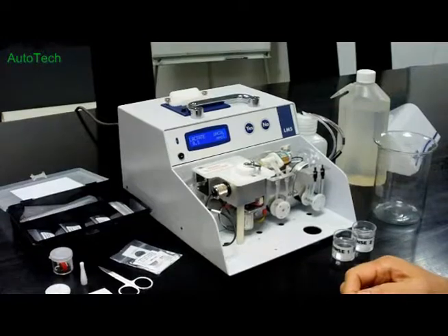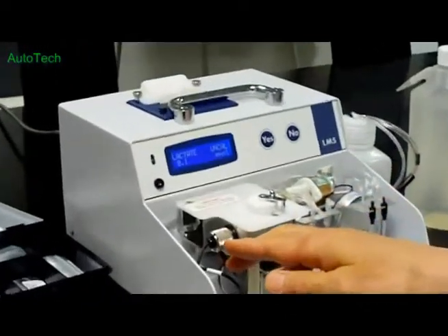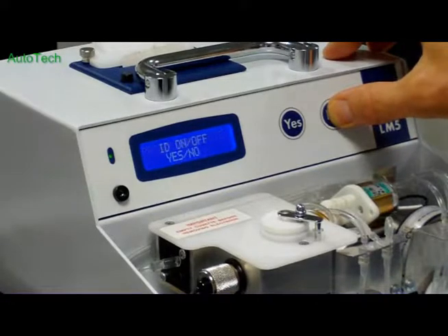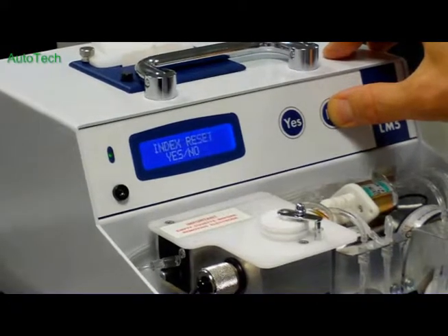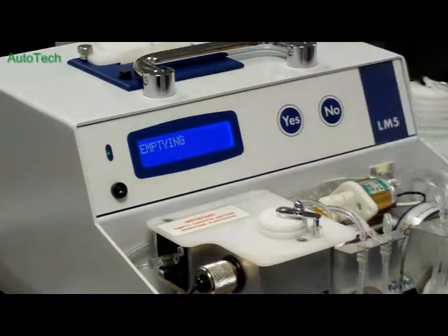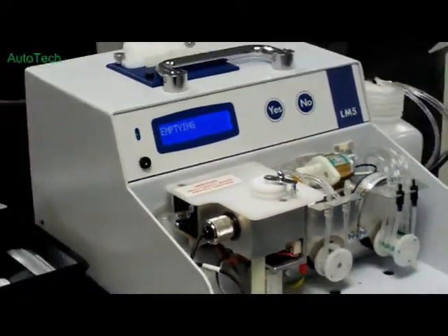And then it's most important that you empty the reaction chamber before removing the electrode. So go through the menu until you come to empty, say yes, this empties the reaction chamber.